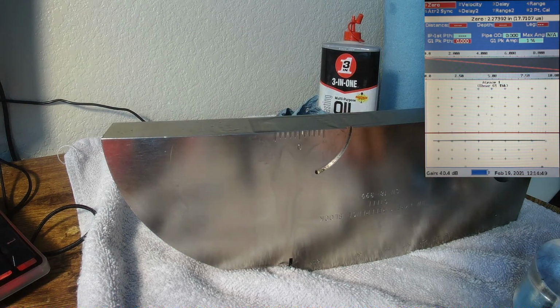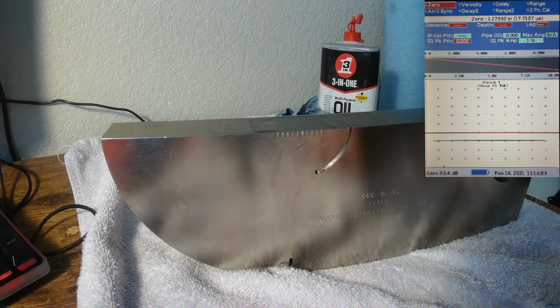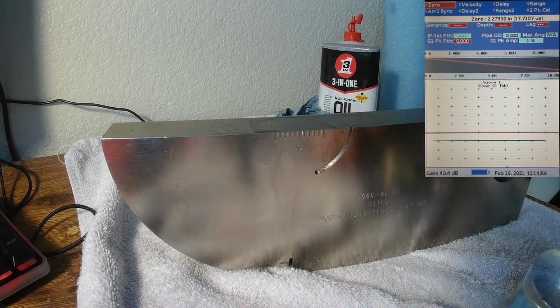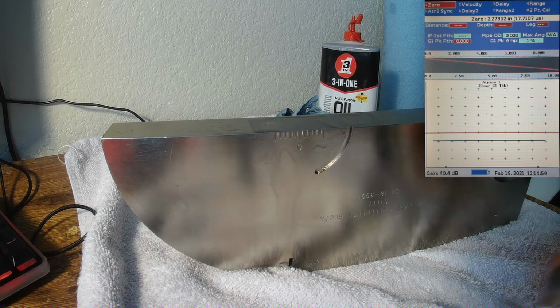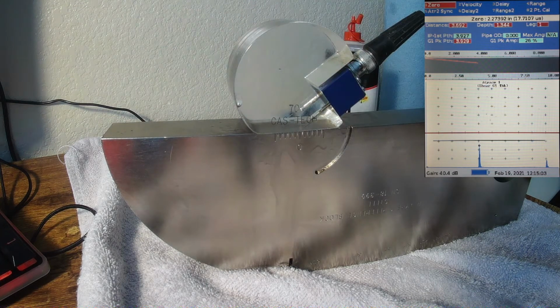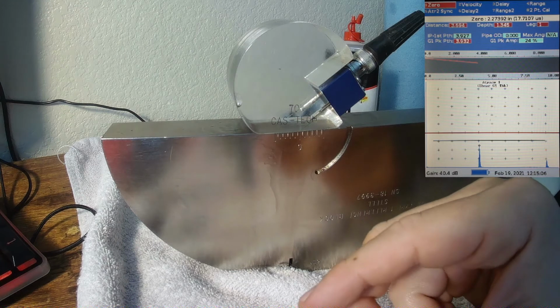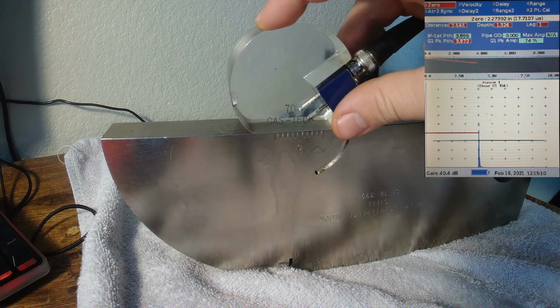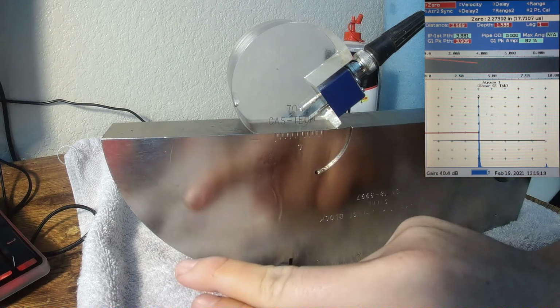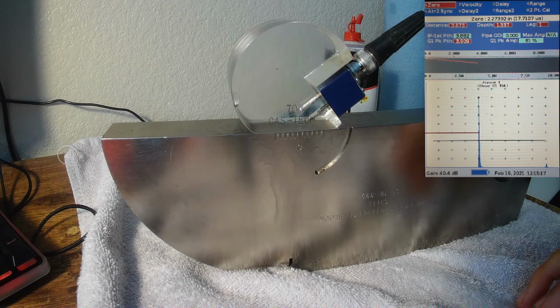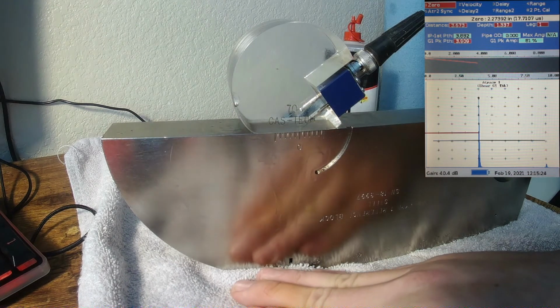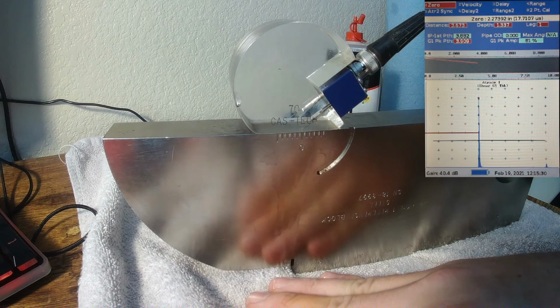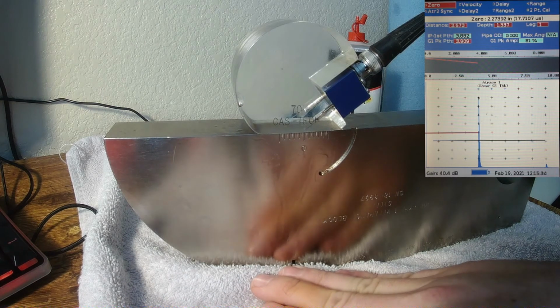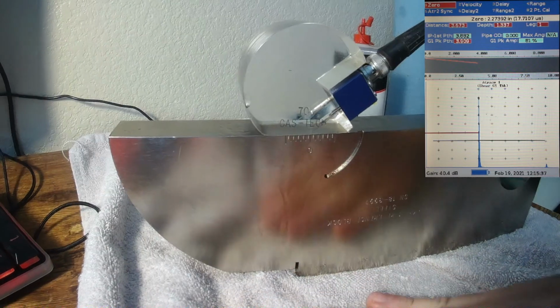And so this is the point of doing the horizontal linearity: to make sure that what you're scanning in the range that you're calibrating for, the thickness range, the machine picks up the right distance. If you're off by a lot, it could be showing you that there's an indication half an inch away from where it actually is. So this is really important.